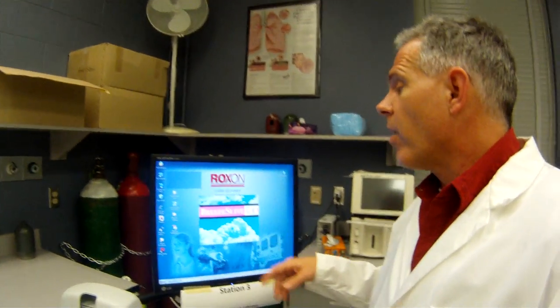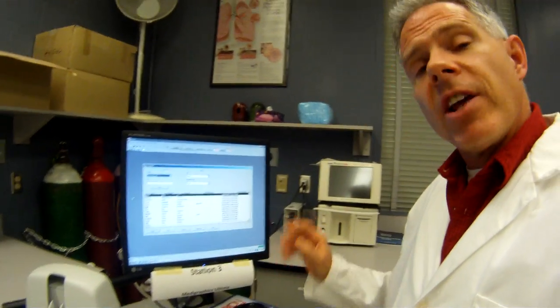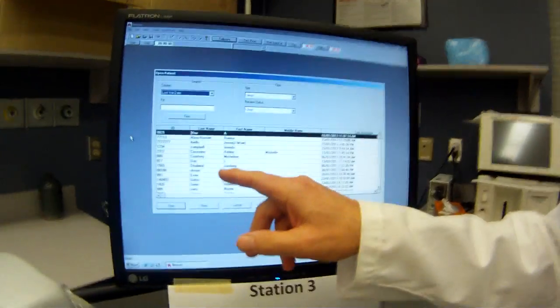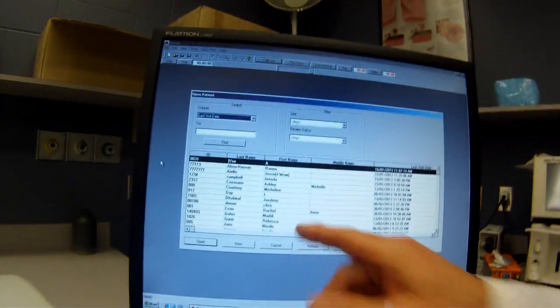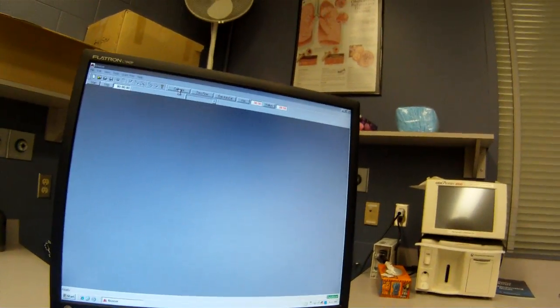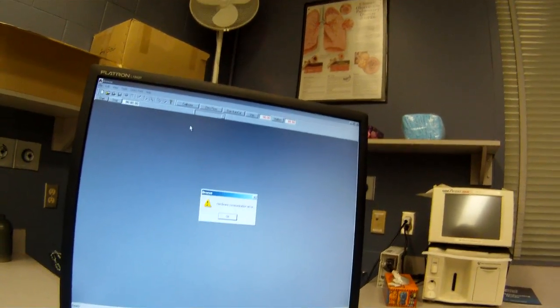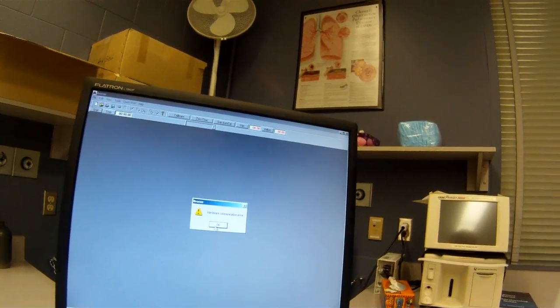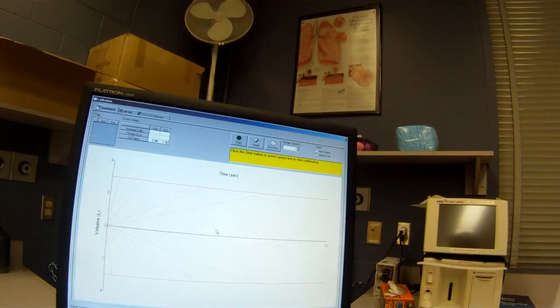And you'll need to know how to utilize this software when you're doing your calibrations and your patient testing. So initially it opens up, as you can see here, we've got our patient data. And I'm going to just cancel out of this right now, because what I want to focus on is doing a basic calibration of our pneumotach. So let's hit calibrate. It comes up with a nice little menu here. Hardware communication error. All right, there we go.